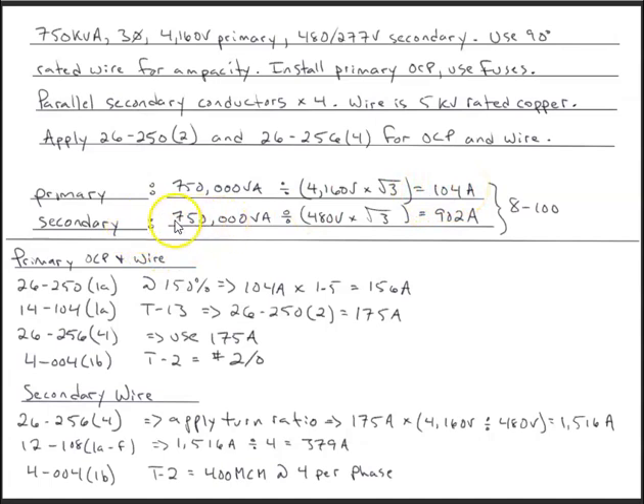On the secondary, we're going to do the same thing, 750,000 volt amps divided by 480 times the square root of 3 gives us 902 amps on the secondary. Now always remember, most of our code calculations are all PEI based, right? Power equals voltage times current. That's what we've been doing the whole time. That's what you will always do when we're dealing with code, and this is regulated under 8100. And when we look at the language of 8100, that's exactly what it's telling you. When we're calculating for currents on loads expressed in watts, we're going to apply certain voltages.